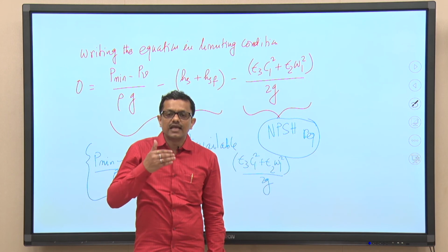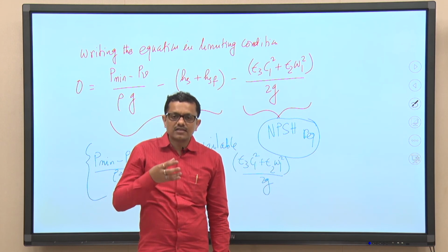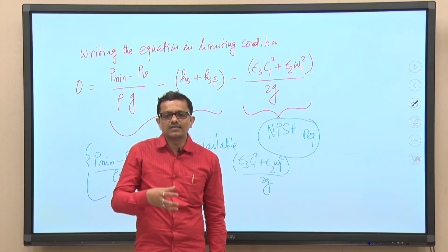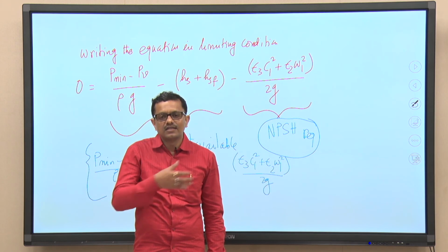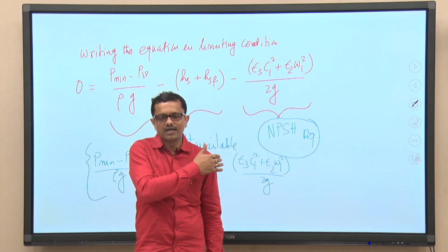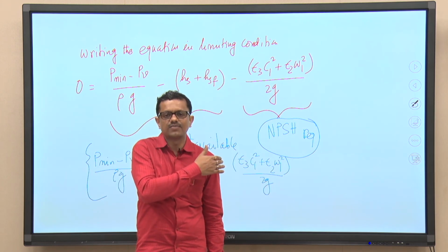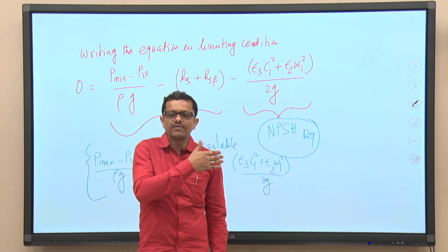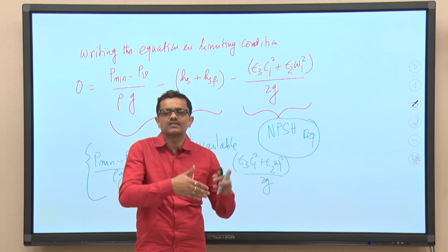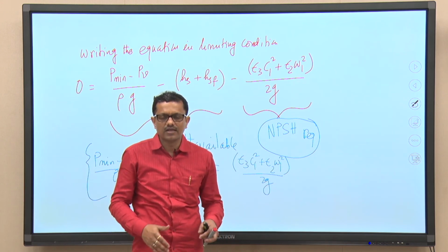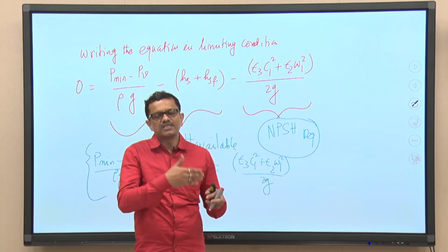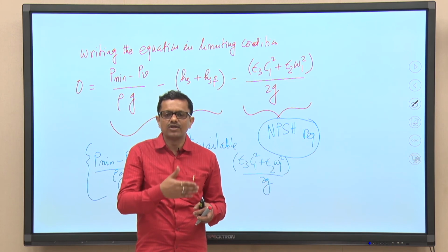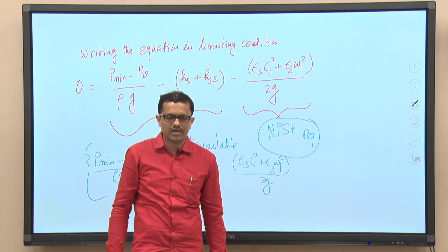Knowing the NPSH required, a system designer should design the system, considering the suction height or static height of the suction pipeline and the presence of valves and bends, so that NPSH available, which depends on the site in which the pump is installed, is sufficient. The system designers should design the system accordingly, so that cavitation can be avoided.